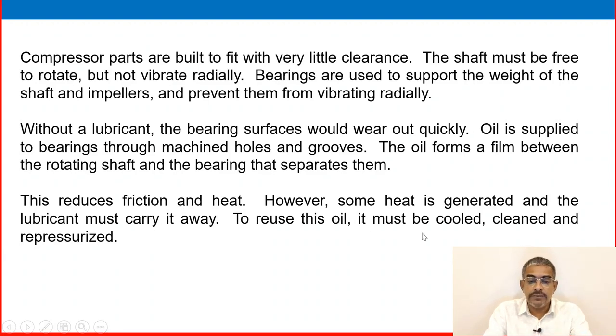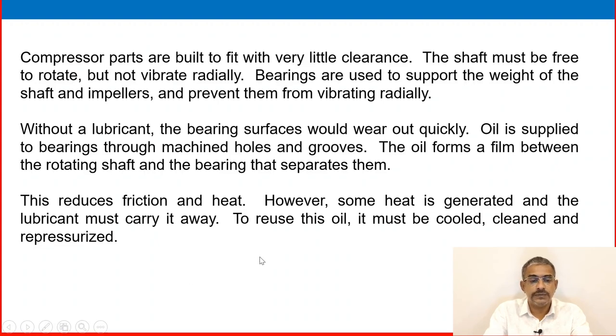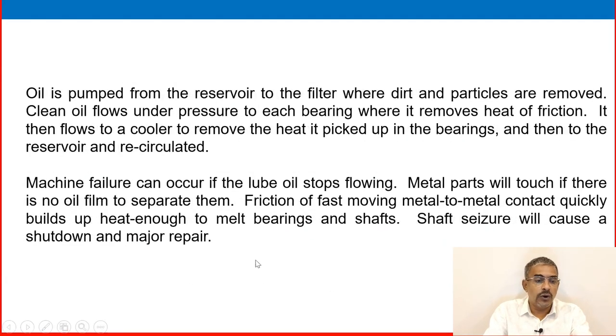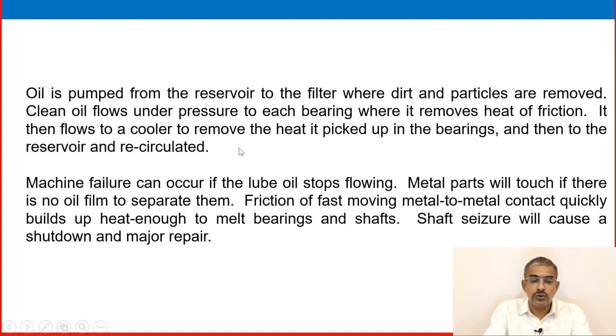The oil forms a film between the rotating shaft and the bearing that separates them, reducing friction and heat. Some heat is generated and the lubricant must carry it away. To reuse this oil, it must be cooled, cleaned, and re-pressurized. Oil is pumped from the reservoir to the filter where dirt and particles are removed. Clean oil flows under pressure to each bearing, where it removes heat from friction, then flows to a cooler, and then back to the reservoir.